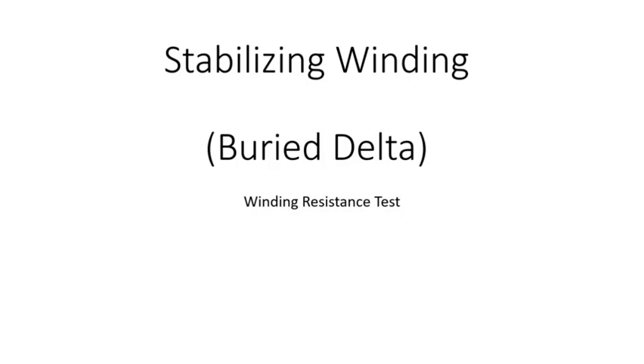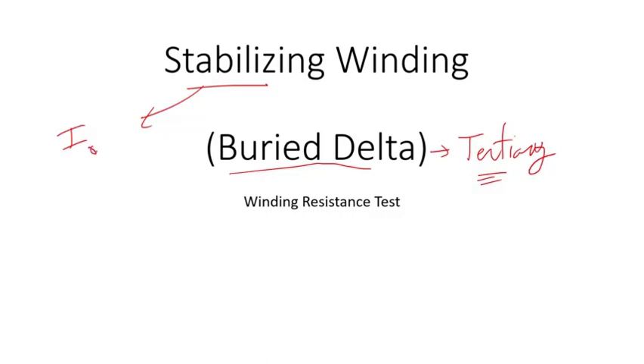In this video, I'll talk about stabilizing winding, which is also known as buried delta winding. Some people might refer to this as tertiary, but as I explained before, there's a difference between stabilizing and tertiary. Stabilizing winding is there just for zero sequence and also for triplen harmonics, 3rd, 9th, and 15th. Tertiary winding, actually the winding is carrying load, so it's loaded. So there are differences.